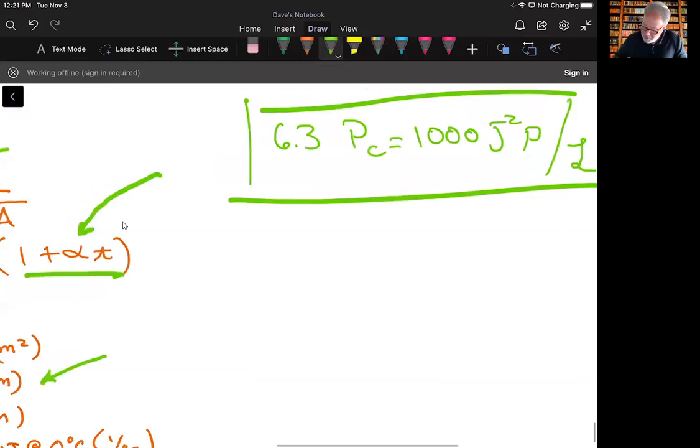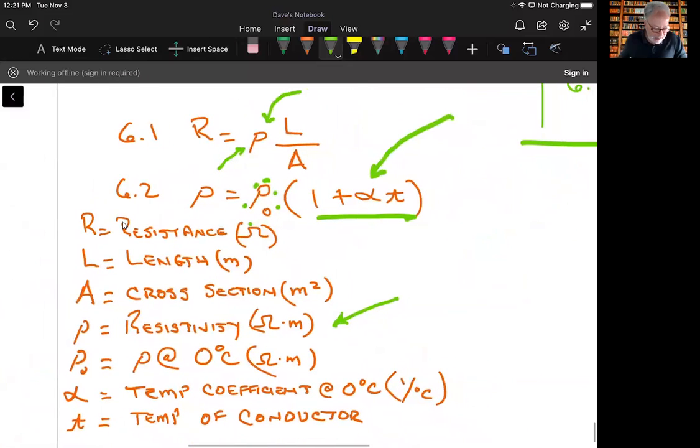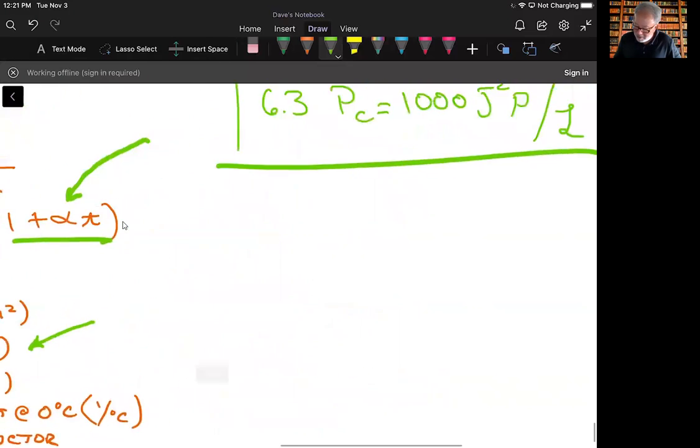Going back to these two equations before we actually plug in and work some problems. In DC motors and generators, copper losses always occur in the armature, the series field, the shunt field, the commutating poles, and the compensating windings, okay? All of those things have copper losses, and these losses show up as heat, causing the conductor temperature to rise beyond the ambient surrounding temperature. And so that's kind of what we're working on here, okay?